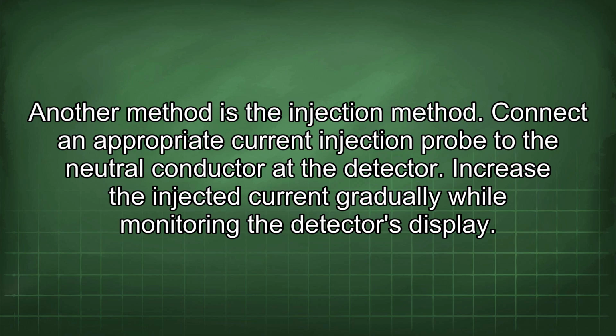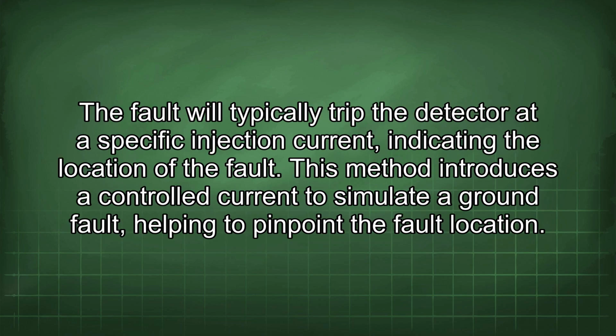Connect an appropriate current injection probe to the neutral conductor at the detector. Increase the injected current gradually while monitoring the detector's display. The fault will typically trip the detector at a specific injection current, indicating the location of the fault. This method introduces a controlled current to simulate a ground fault, helping to pinpoint the fault location.